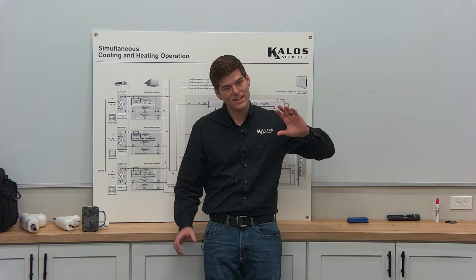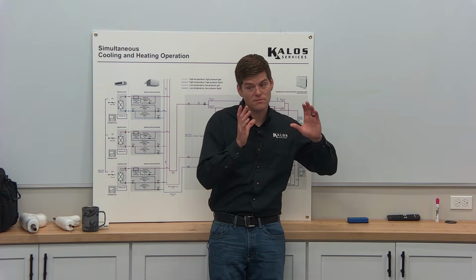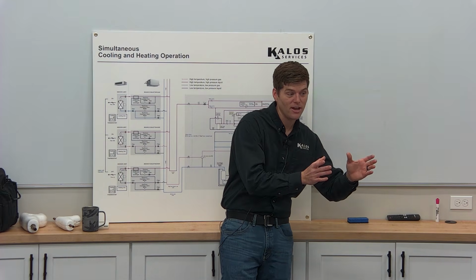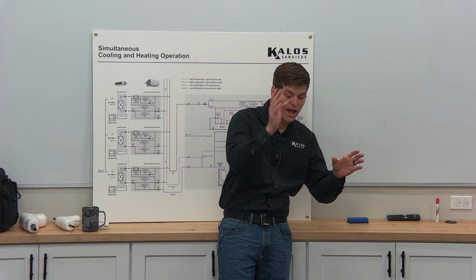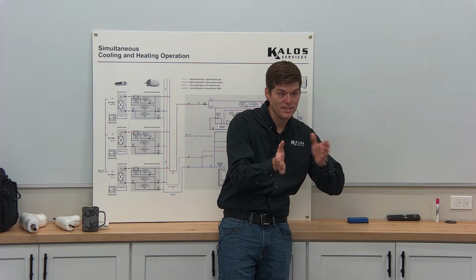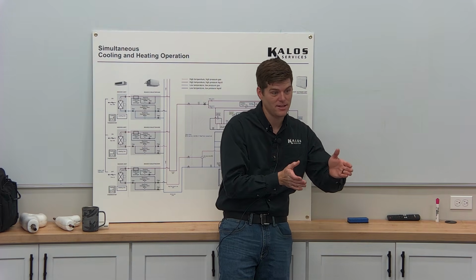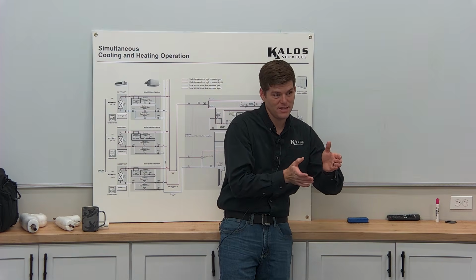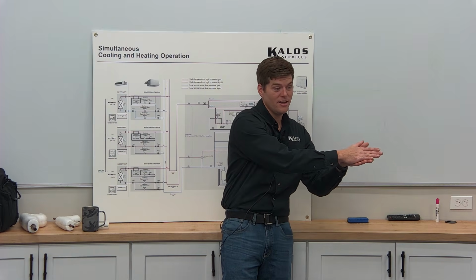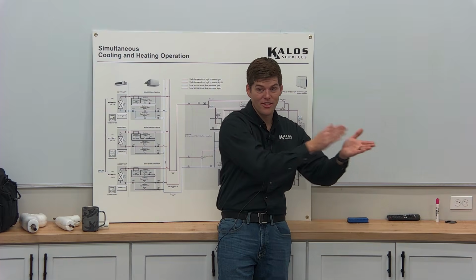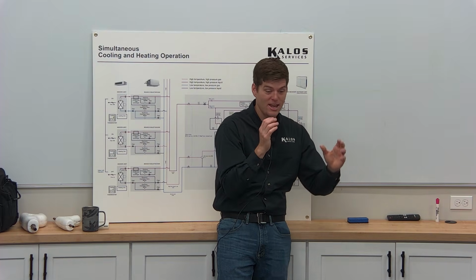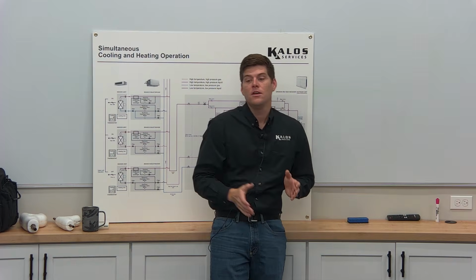Those, they like to claim they have a lot of speeds, but it's a compressor running full max, right? And they bleed hot gas back over into the suction line in time seconds, and that reduces capacity. Those technically aren't different speeds. That compressor runs 100%, and then off. 100% and then off. There's a contactor that pulls in and then it runs full speed.